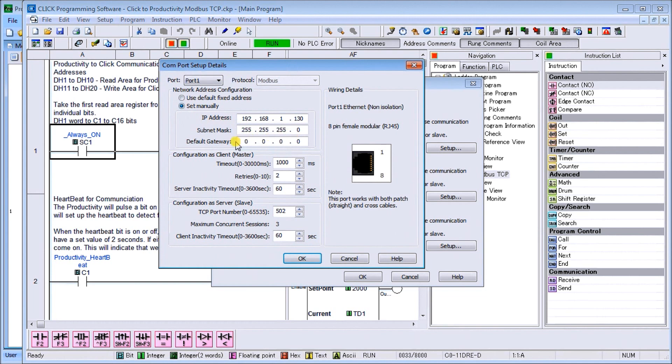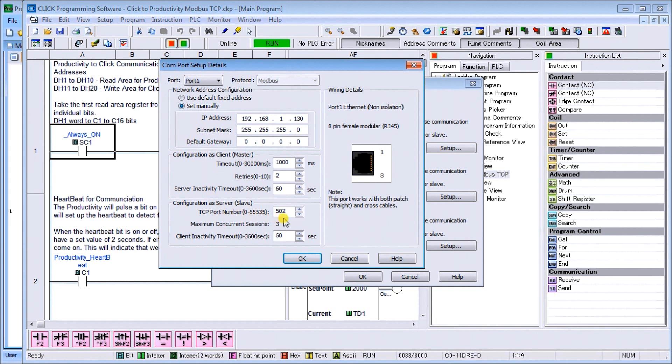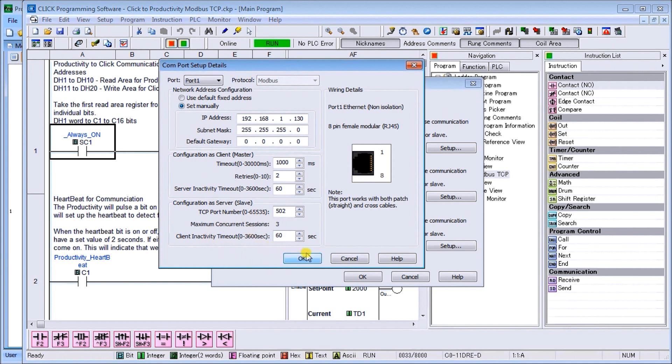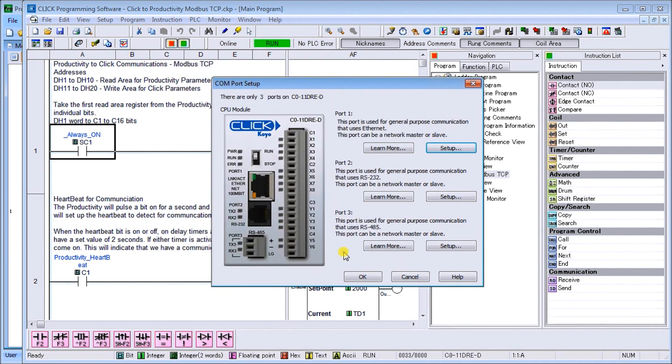The default gateway is 0.0.0.0, which means it does not have exposure to the internet itself. Then we have our timeouts and we'll leave those as default. Under our server, you'll see port number 502 and we'll leave that as default, and client inactivity timeout will leave that at 60 seconds. We'll soon see how that heartbeat works.